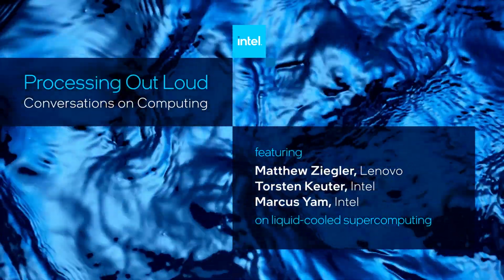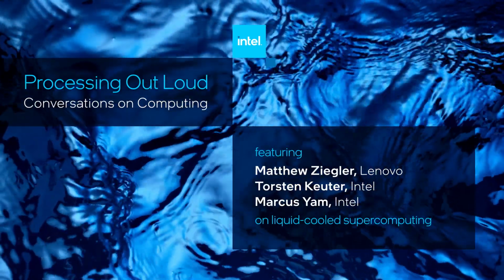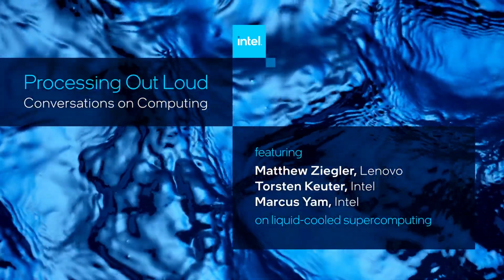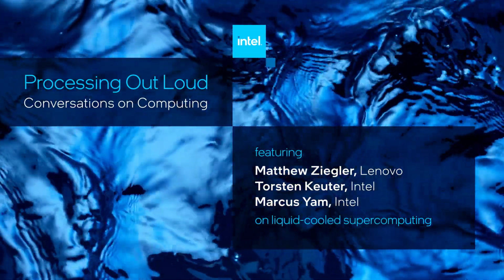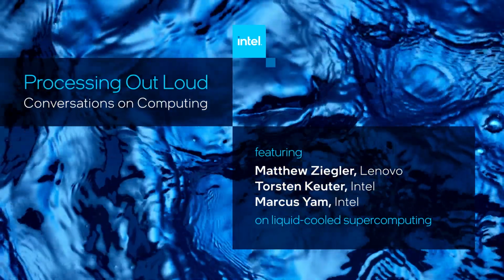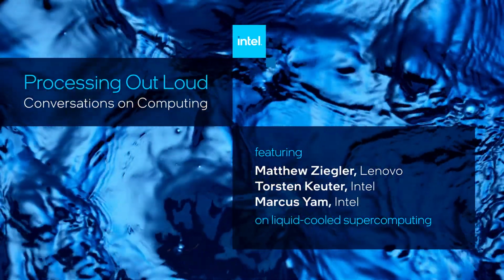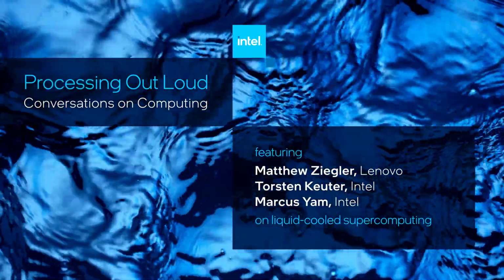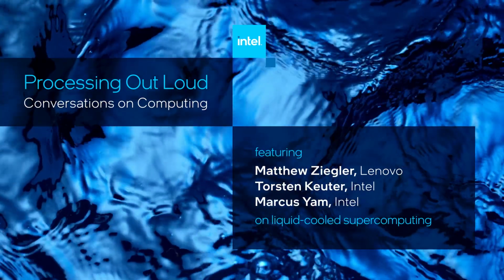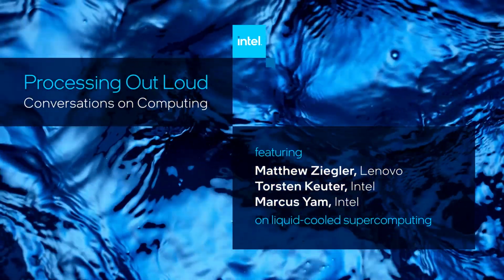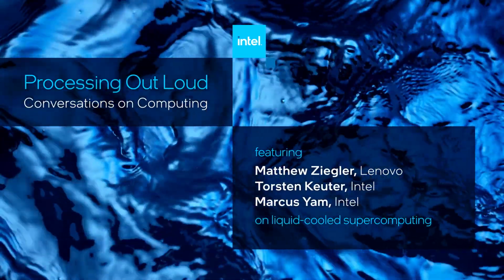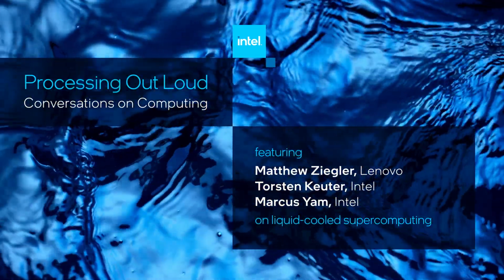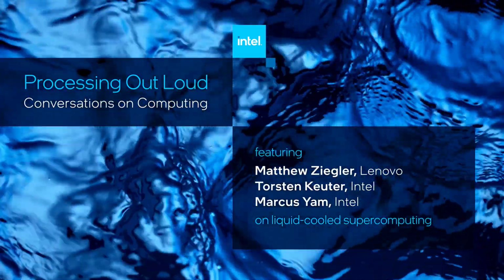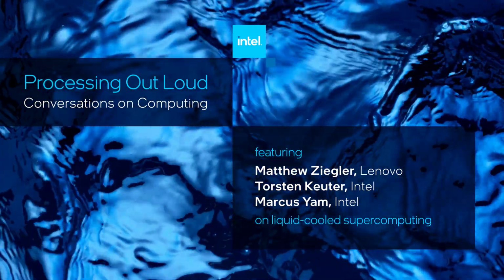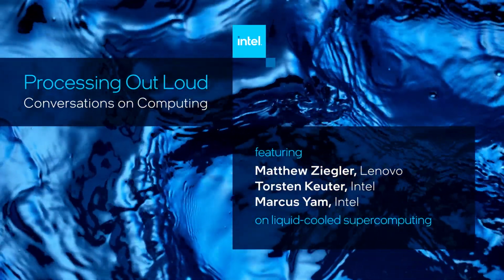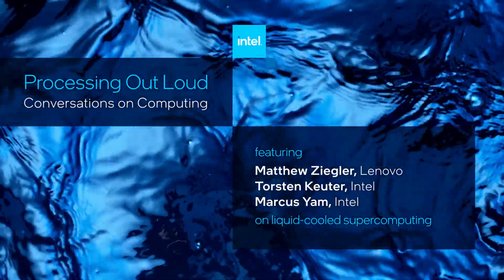It's all about scale. If anybody's been in a data center, think about a gaming PC - how do I deal with one? We are talking about dealing with thousands to tens of thousands. When you start stacking them all together, the amount of heat that gets exhausted... if you've ever put your hand near a gaming PC's exhaust, it's pretty hot. Now times that by 10,000, think of the temperatures you'll get in a room. That's one of the biggest challenges we have, scale, so that we can't be heating up your room. We've been leveraging liquid to actually send it outside of a physical building where we can evacuate that heat into the universe, if you will.